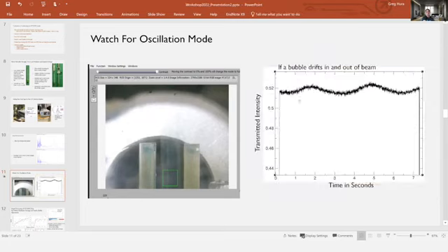But occasionally we get a sample, and maybe Kevin was a victim of this, where you get a bubble or a low density amount of liquid in there. If you look at the transmitted X-ray beam, the plug of sample comes in and out, and the bubble comes in and out as well, right? So you get these oscillations during your collection. This is something we wouldn't have added to the pipeline if it didn't work in our hands, but if you've got something pretty sticky, or things aren't quite right, you might fall victim to some of this, so look out for it.